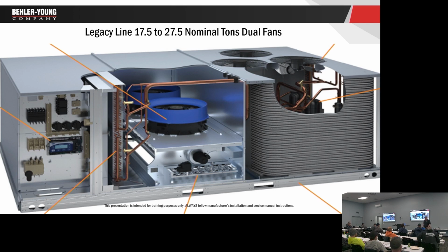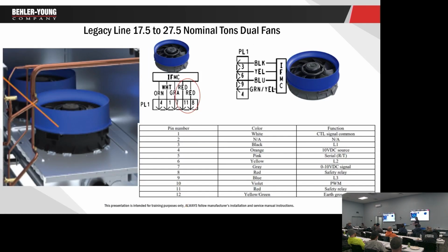This one here simply has gray, orange, and white, yellow and black. I do not have the safety circuit. This is the 3 through 6 ton. Sorry about that. So, when I look at the big units, they'll also have 2 red wires going to the motor. And that's the safety circuit. Like I said, it's not an overload. It's actually an electronic safety circuit. It's a normally closed relay. And I think when it's creating DC volts, it keeps the relay closed. And what it does is if for whatever reason it faults, it opens the relay, locks the motor out.